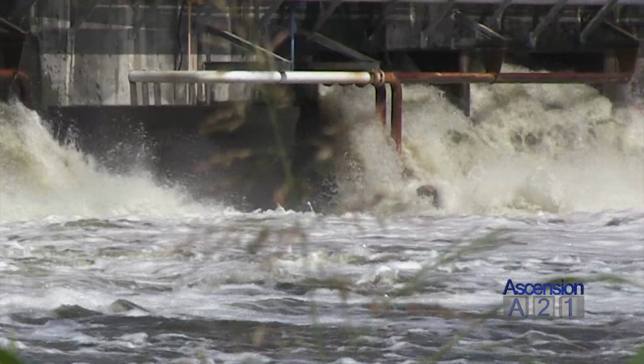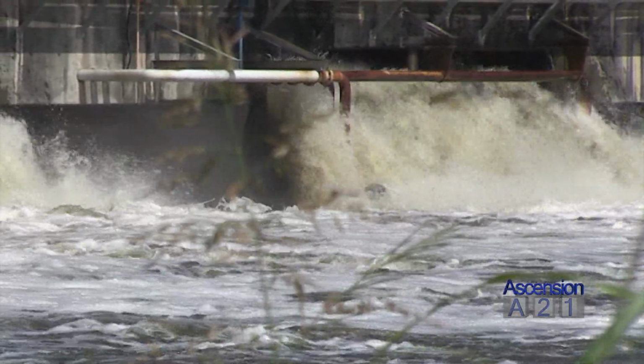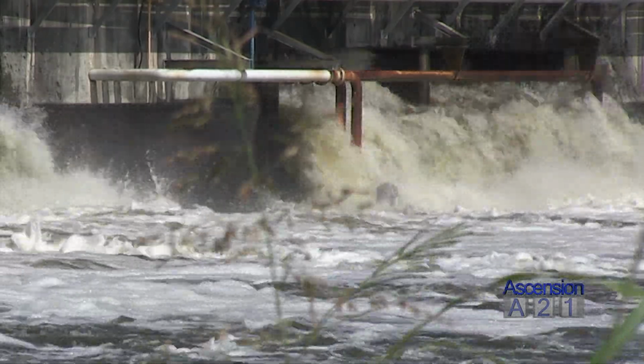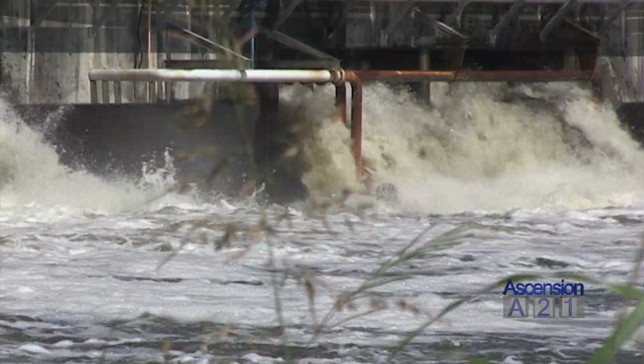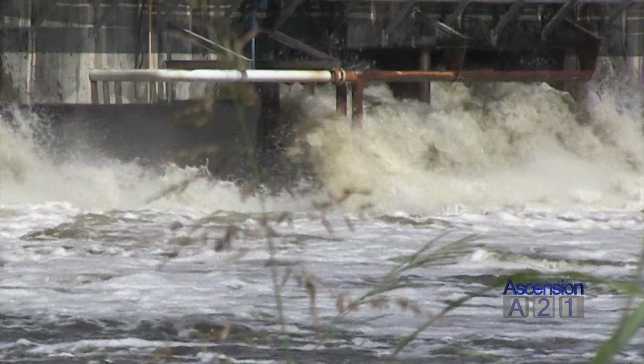And how much water can just one of these pumps move? One pump, by the manual, at 960 RPMs, will turn 448,800 gallons a minute. I'll round this off at 500,000. So if all 6 of them are running, you're looking at 3 million.